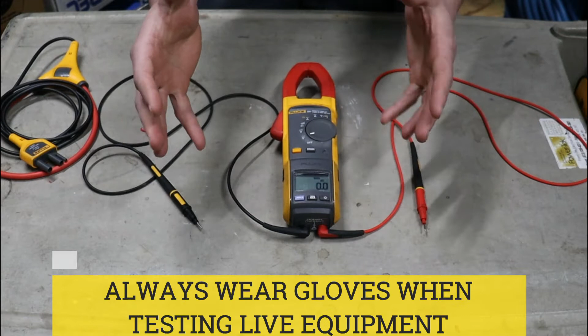Voltage. We don't have anything live to test right now, but we'll talk a little bit about safety when you're going to do live testing, test voltage. You always want to have on your gloves, your calibrated gloves, just to protect you from any potential shocks, or if you're in there close to bus bars, you want to have that protection. So that's quite important. Also, you want to have your arc flash gear on. You have to read the label on the front of the equipment you're in. It'll have an arc flash sticker on it. It should have a cal rating, and that's what you base the type of suit and PPE required to enter that live.